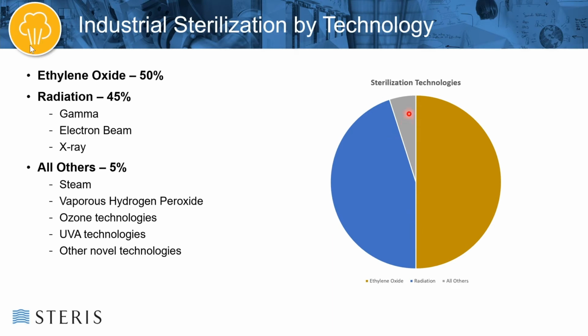So you can see that steam is not a really big technology that's used, but there are some times when it is needed. Jokingly, I told one of my colleagues the other day that I was going to subtitle this presentation 'Sometimes EO and radiation just doesn't work.' That does actually happen, where there are some products that you simply can't process in EO or through radiation. And oftentimes steam becomes the next viable alternative for sterilization of that type of device.